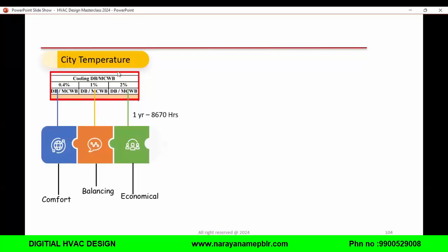Next, when you refer to any city's temperature conditions, we will have three parameters. One is for comfort, 0.4, which will be mentioned like 0.4 DB. These are dry bulb and wet bulb, 1% dry bulb and wet bulb, and dry bulb and wet bulb. So this is designed for comfort, this is for balancing, and this is economical. What does it mean? Comfort, balancing, and economical.